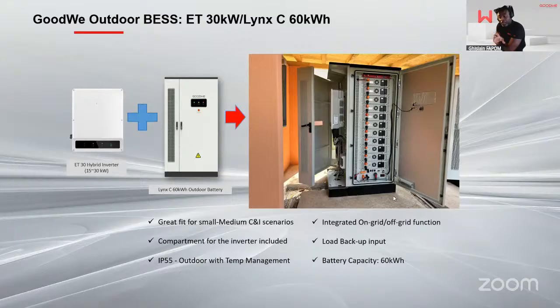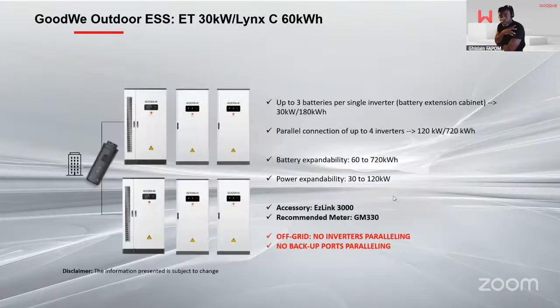And then at cabinet level, you're also going to have monitoring of the whole cabinet to make sure that the temperature doesn't go outside of the acceptable parameters. So it's a self-sustained cabinet, IP55, with 60 kilowatt hours of battery and up to 30 kilowatt for the inverters. Now, again, the cabinet can also be put in parallel using the EZLink 3000, a maximum of 4 inverters as before, because it's the same inverter we're talking about. The size will then reach 120 kilowatts to 720 kilowatt hours of storage.